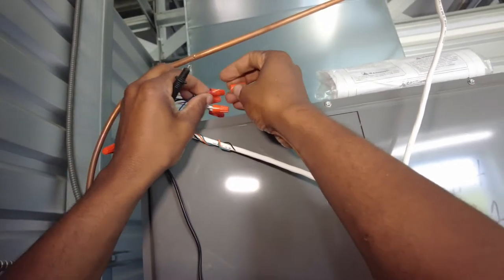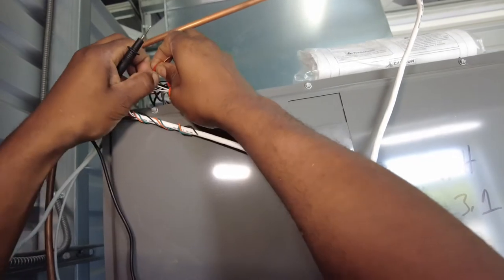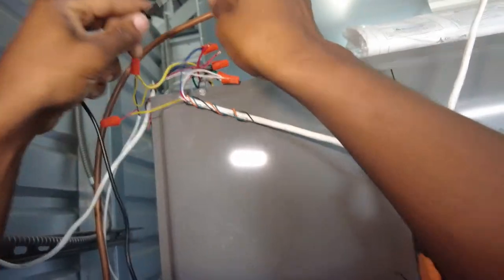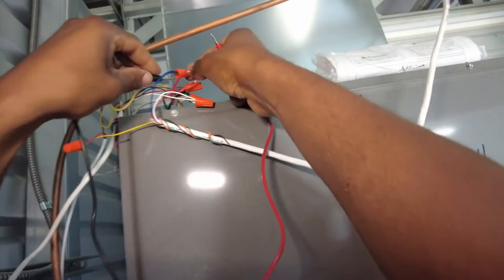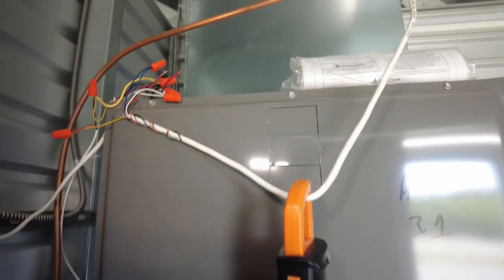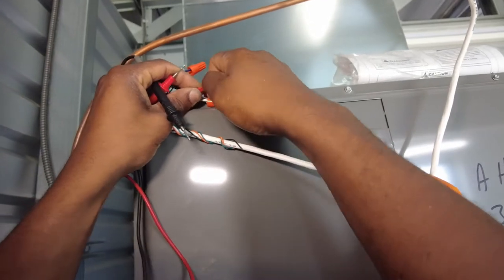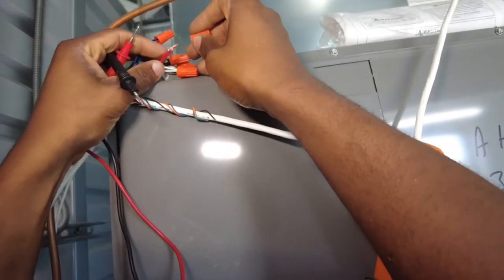I'm just connecting to see what I'm reading across. Let's see what I'm getting here. That's 24 volts, still 24 volts. Seems kind of low, usually between 26 and 28 volts. So 24, but we're seeming to be getting a drop somewhere.